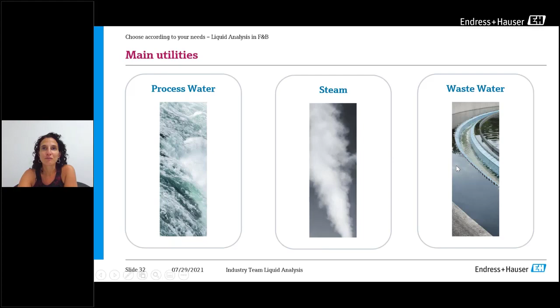Talking about process water monitoring, the main parameters monitored globally are disinfection in general, because in some cases we need to disinfect water taken from a lake or a well before it's treated and used for food production. For that we measure chlorine dioxide, free chlorine, and ozone. We also measure conductivity, turbidity, pH, and where needed with analyzers, hardness, iron, chrome and aluminum.